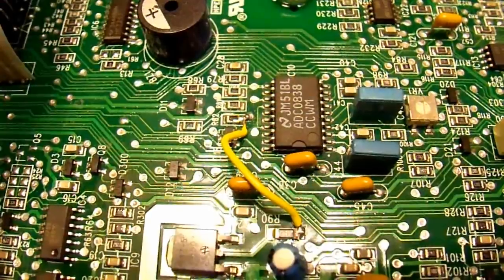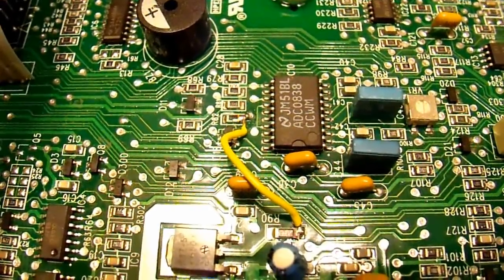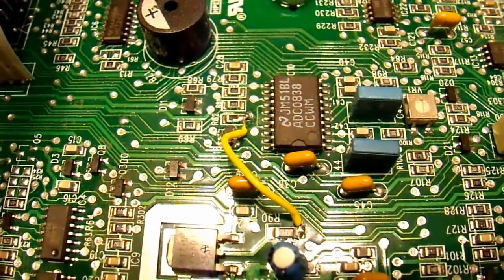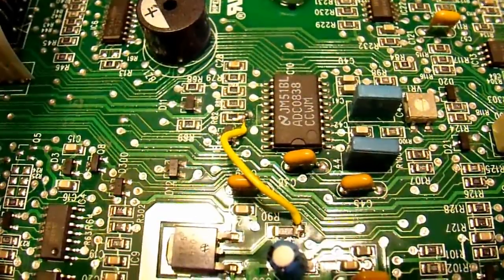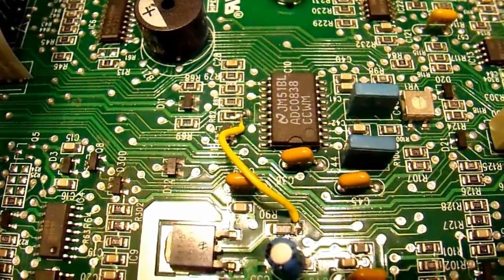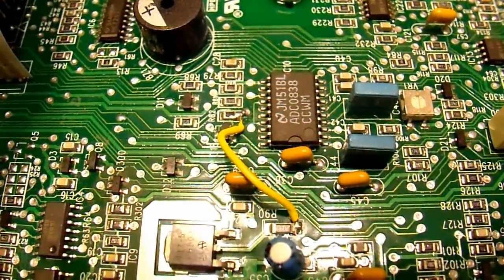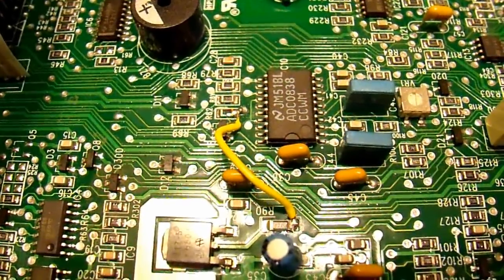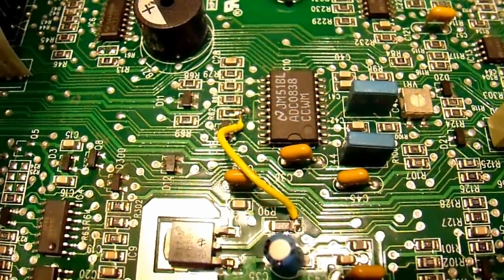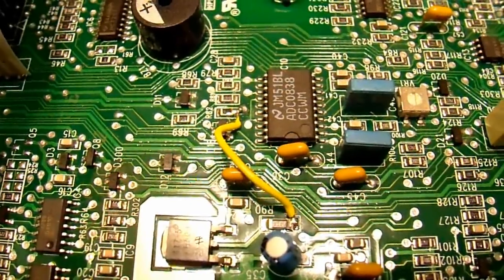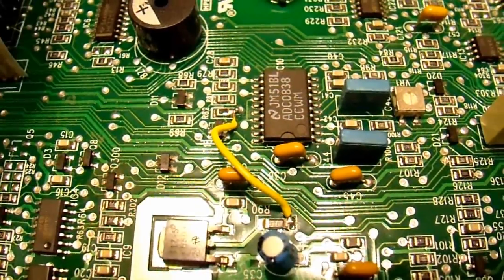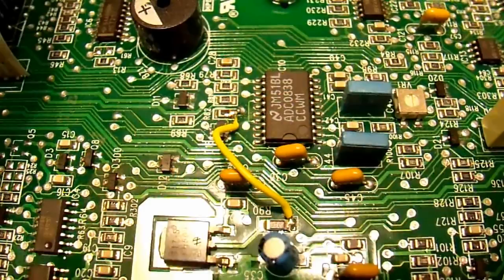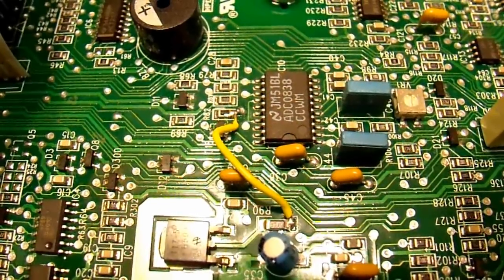And there's the jumper that I added that will force this UPS into slave mode while still maintaining its sync-to-mains capability. And what I mean by slave mode is that it will never go into pass-through mode where it ties the incoming mains to the outgoing power. And it will also never go into boost or buck mode. It will only be in inverter mode. That's the only mode that will be allowed. And that's what I want if I'm going to sync both of these together.